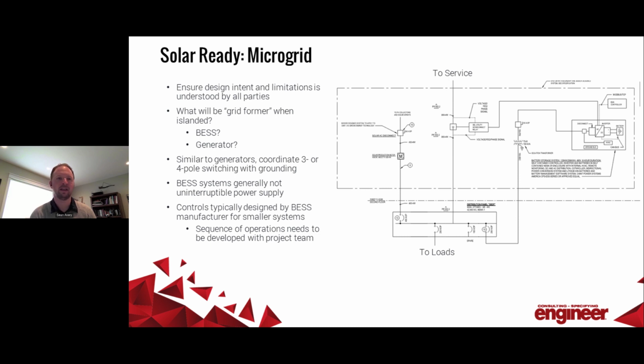The other thing I'll talk about here is grounding. Make sure to keep track of your system grounding, much like you do with a generator, whether you're doing 3-pole or full 4-pole switching, to make sure you maintain a system ground. I've seen issues before where that's not been maintained properly, causing problems with some single phase loads.